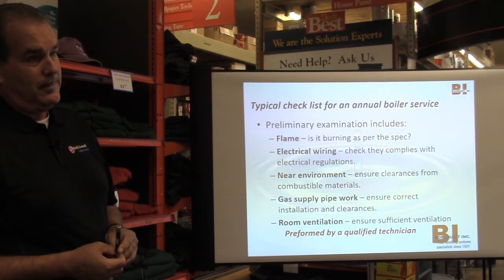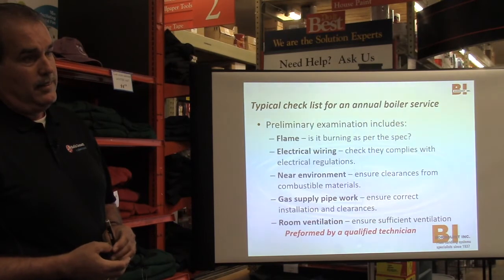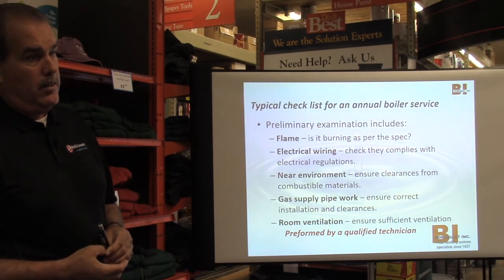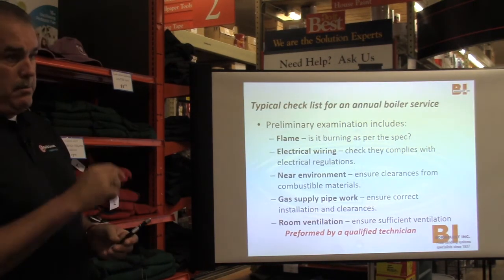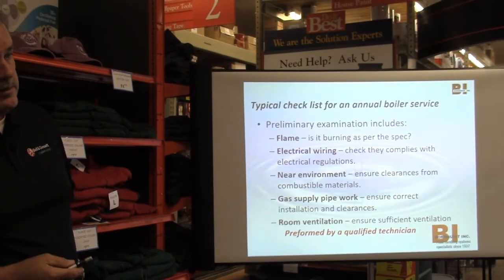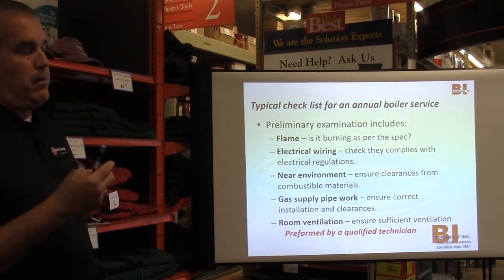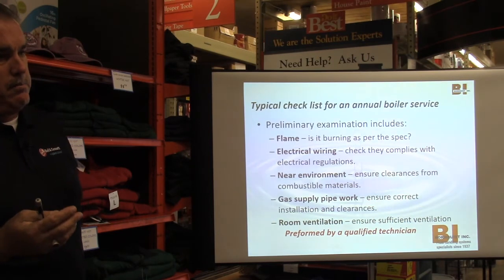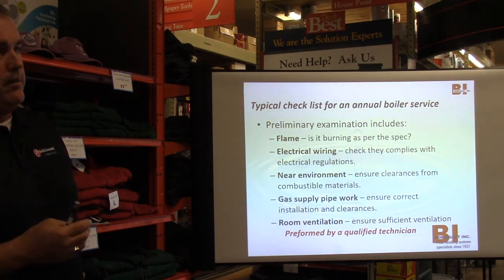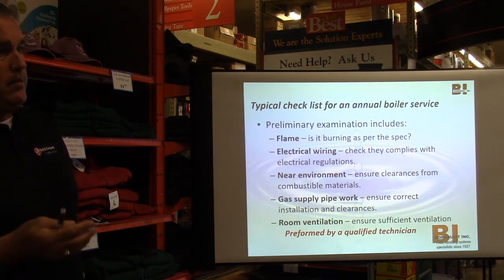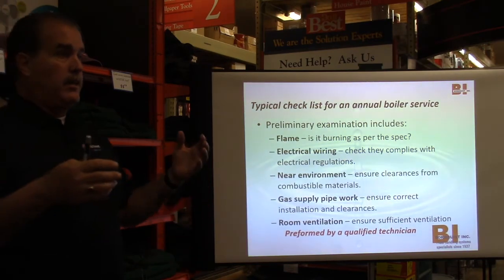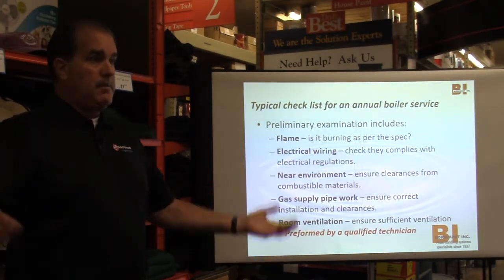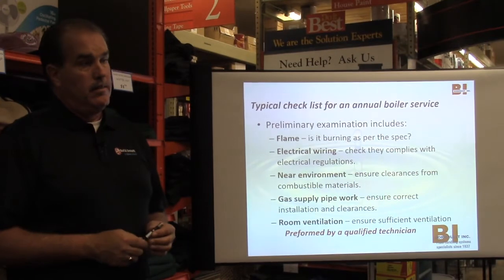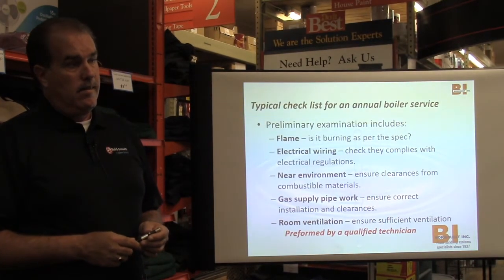Part of this is tested by an expensive instrument. A $1,000 instrument is what's needed for this, right? To adjust combustion, yes. Just combustion, which is flame and ventilation. Right. And atmospheric boilers aren't as sensitive to it as modulating boilers. Okay. To emissions. But atmospheric boilers are exactly what they are. Atmospheric. They require atmosphere to run. So if it's checked once, how often would it need to be checked?